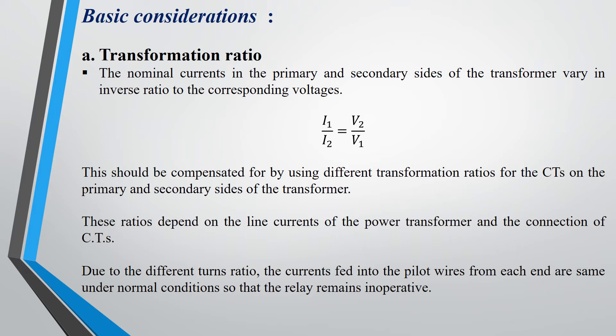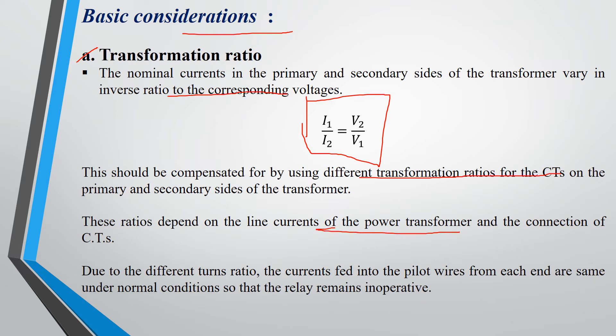There are basic considerations that need to be taken care of while applying differential protection to transformers. The first one is transformation ratio. We know that a transformer is used for increasing or decreasing voltage or current level, and therefore the primary and secondary currents are not the same, as they vary in inverse ratio to their corresponding voltages. Therefore, to compensate this, we need to apply different transformation ratios for the CTs — meaning the CT ratios applied on both sides of the transformer must be different. These ratios depend upon the line current of the power transformer and the connections of the CT, whether in star or delta.